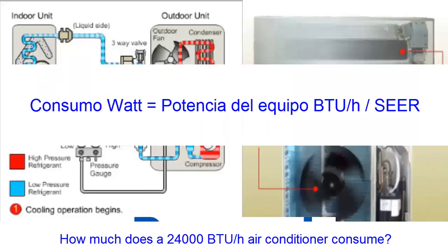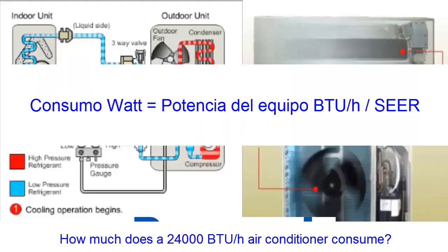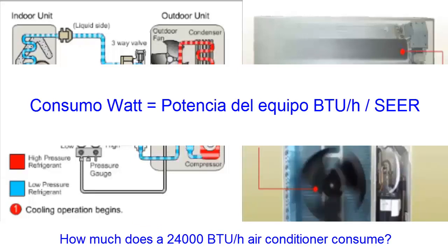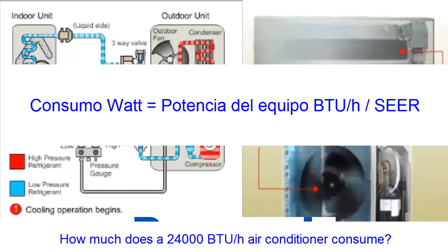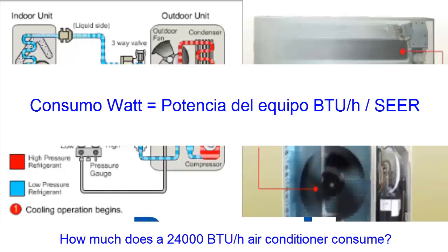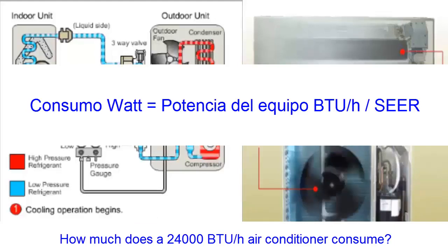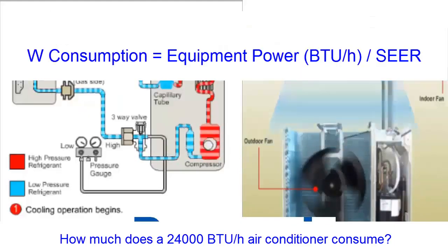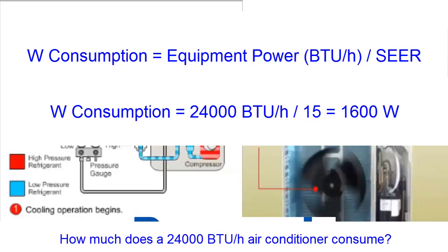The equipment's power in BTU per hour is divided by the SEER value to obtain the average power in watts that the equipment consumes. With the identified electrical power, you can consult the current consumption value in the amperage tables based on the voltage and phase, whether it is single phase or three phase.